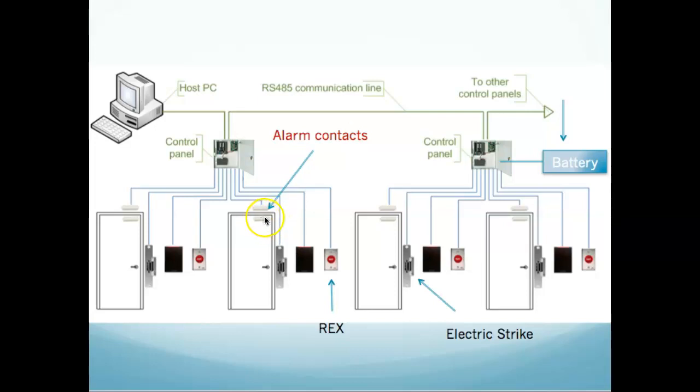They're only usually about 2 or 3 inches. But they're alarm contacts. Essentially, when the door opens, these two things separate. This is a standalone magnet, in this case screwed to the face of the door. This one is up above it on the door frame. When these two things separate, it says, we're separated, and it goes up here and says, you have an alarm. And it goes up to the host and says, you have an alarm.